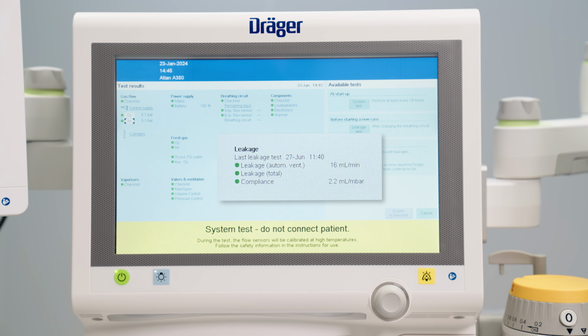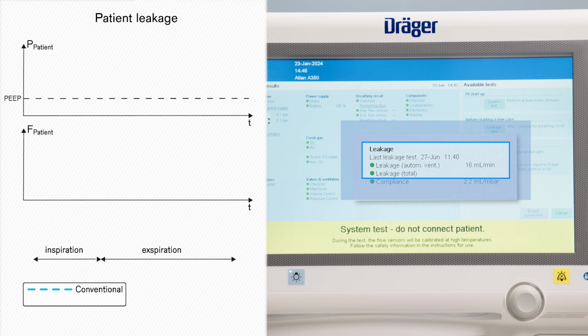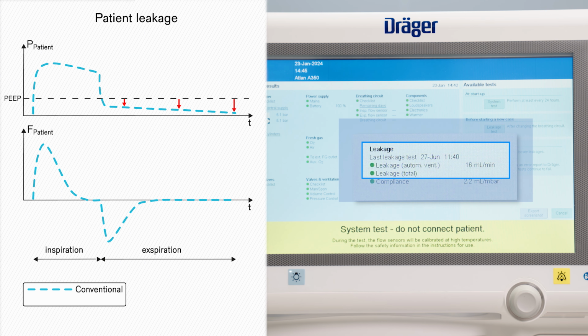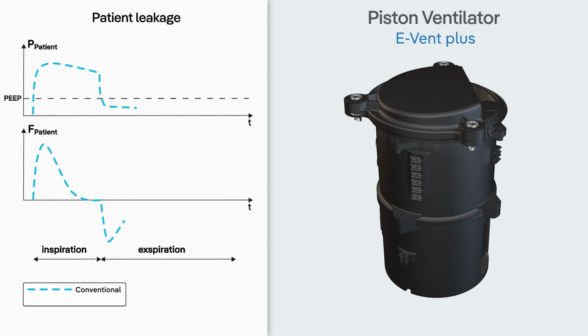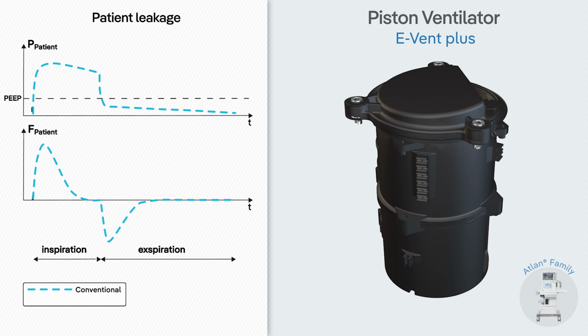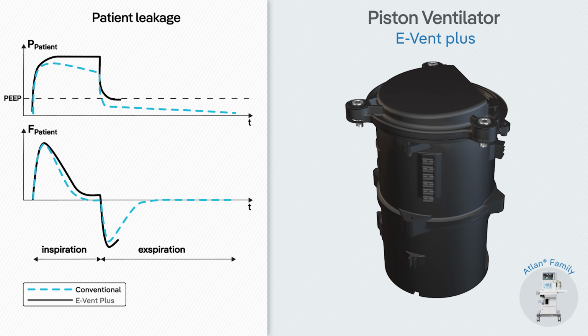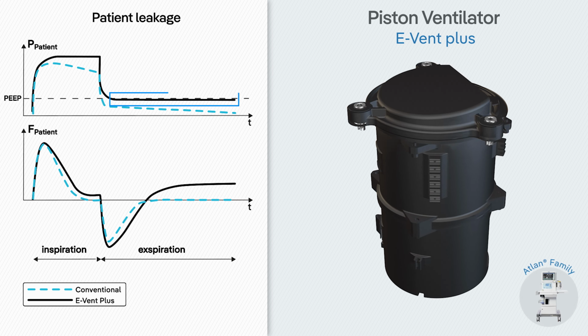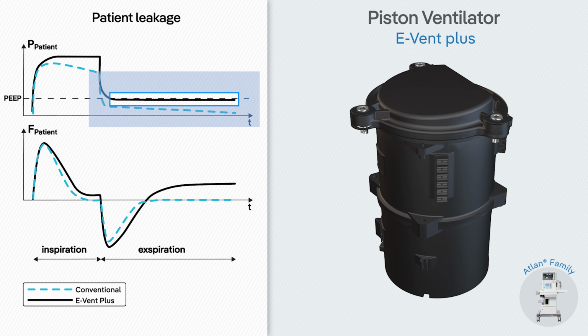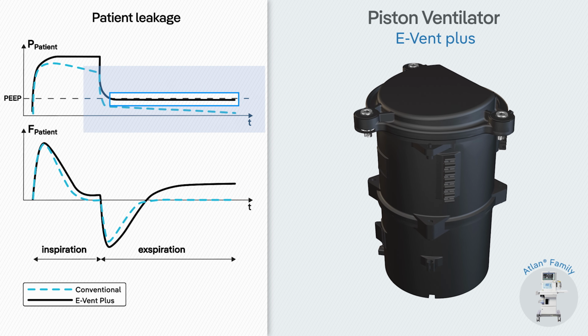Leakages can have significant influence on ventilation. Although system leakage can be identified during the leakage test and compensated by correspondingly increasing tidal volume, this does not prevent the PEEP from falling or even diminishing between expiration and inspiration. The E-Vent Plus piston ventilator in Atlan family devices actively holds PEEP levels by moving the piston upwards during expiration and thus compensating for lost volume due to leakages.